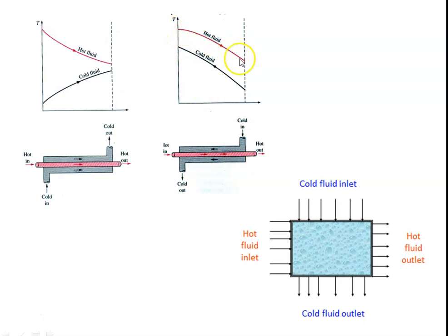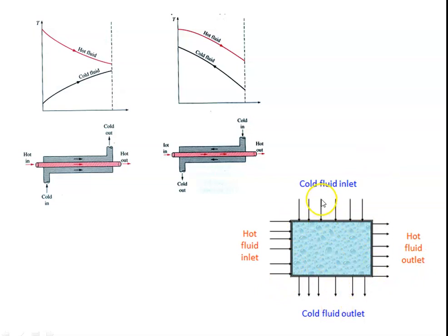In the counter flow temperature profile, the hot fluid temperature decreases from inlet to exit and the cold fluid temperature increases from inlet to exit. In the cross flow heat exchanger, the cold fluid enters at the top and leaves at the bottom, while the hot fluid enters at the left side and leaves on the right side — the flow directions are perpendicular to each other. So: same direction is parallel flow, opposite direction is counter flow, and perpendicular direction is cross flow heat exchanger.